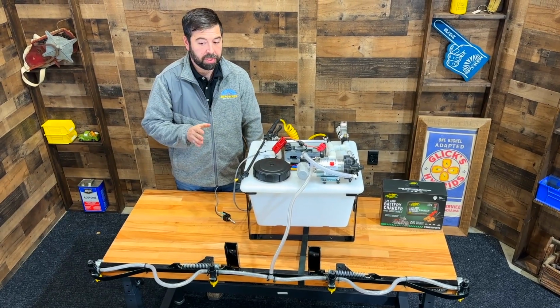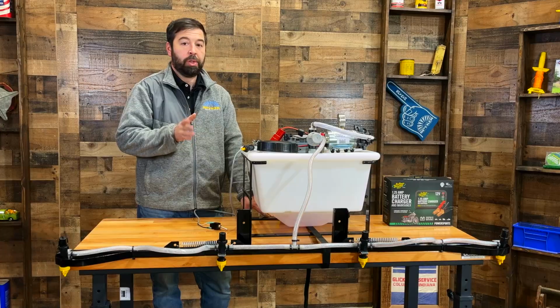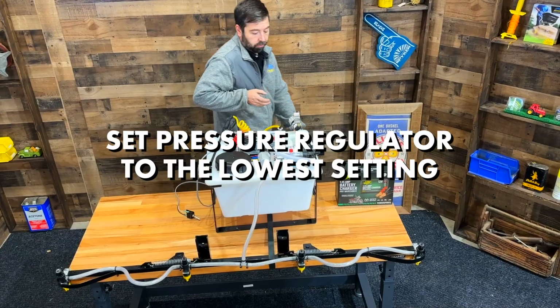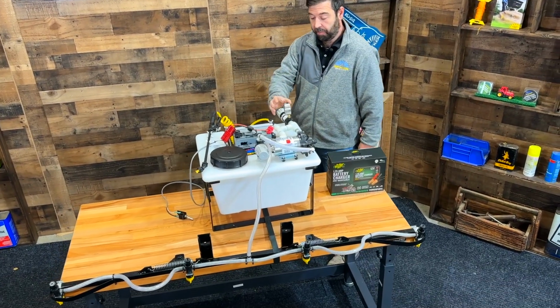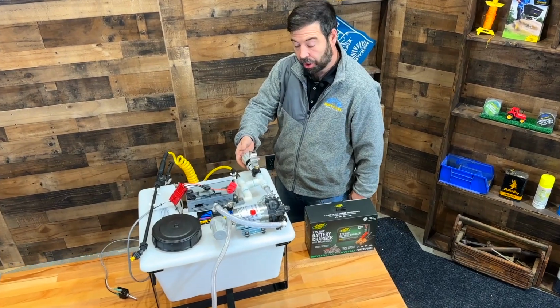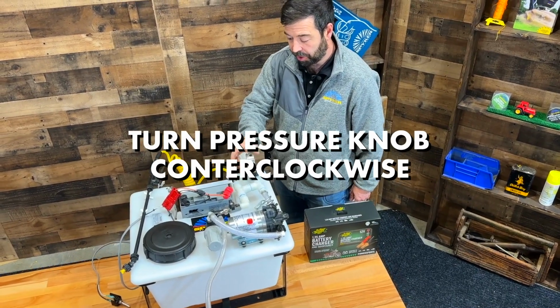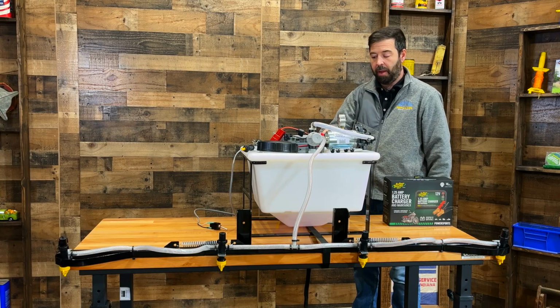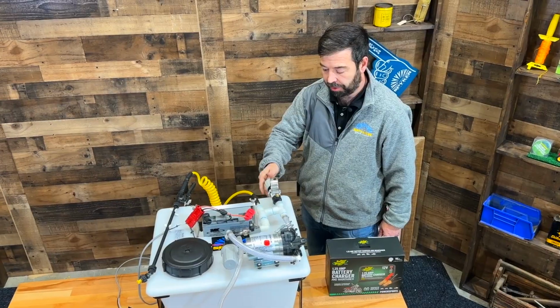Before we start up the pump, we want to set our pressure regulator to the lowest setting. You can do that by turning the pressure regulator knob counterclockwise all the way as far back as you can. You can actually remove the knob, so just keep turning it back until it's loose.